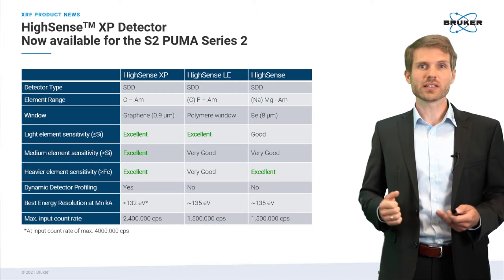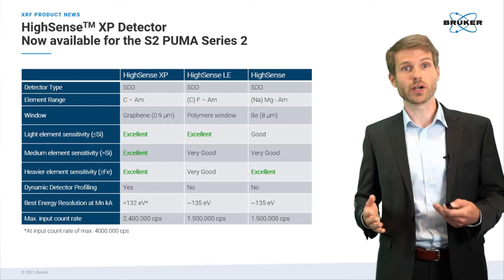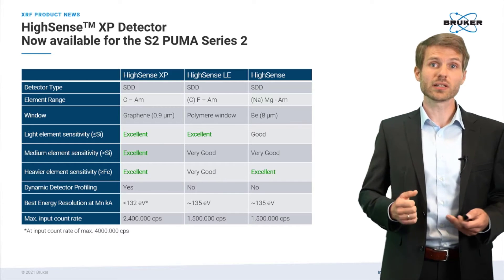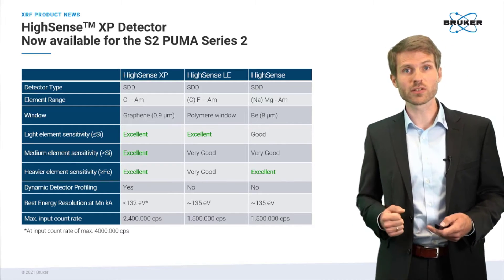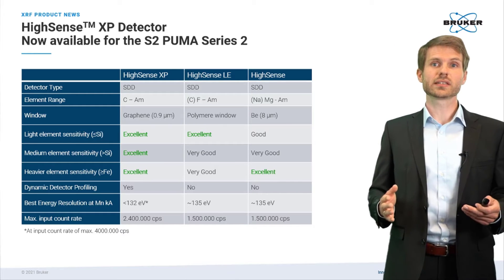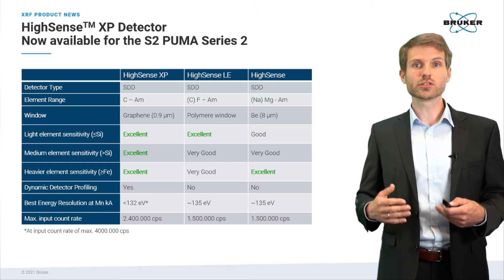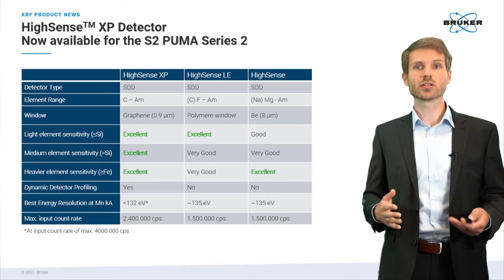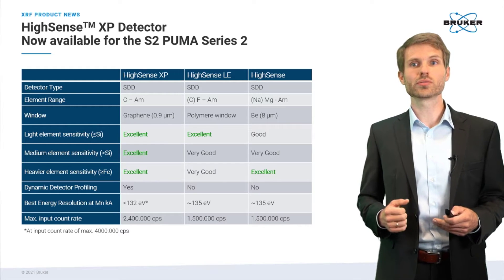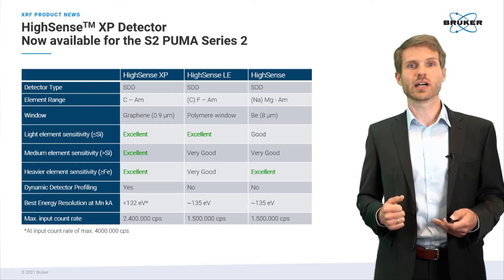Our standard HighSense detector with a beryllium window is also an excellent solution for various applications, in particular when it comes to medium and heavy elements. However, exclusively available for the HighSense XP is the new detector profiling feature, which allows you to boost the count rate up to 2.4 million counts per second or enhance the energy resolution below 132 eV at Mn Kα.